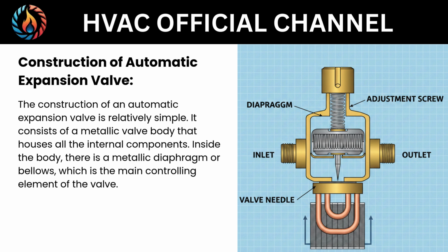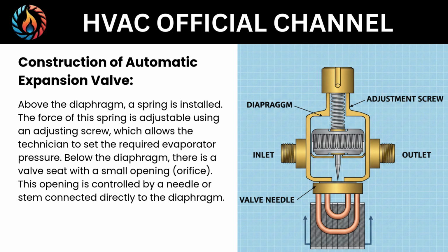Construction of automatic expansion valve. The construction of an automatic expansion valve is relatively simple. It consists of a metallic valve body that houses all the internal components. Inside the body, there is a metallic diaphragm or bellows, which is the main controlling element of the valve. Above the diaphragm, a spring is installed. The force of this spring is adjustable using an adjusting screw, which allows the technician to set the required evaporator pressure. Below the diaphragm, there is a valve seat with a small opening, the orifice.